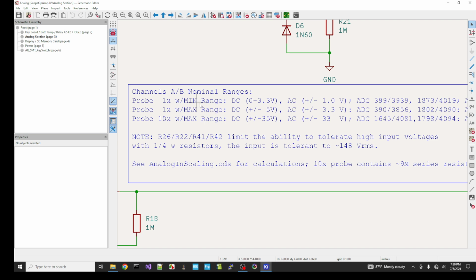On the minimum range, which is the most sensitive, on DC we get 0 to 3.3 volts DC. Then the next range would be plus or minus 5 volts. And then finally, with the 10x probe in the 10x position, we get plus or minus 35 volts. And then AC coupled, as opposed to DC, we get plus or minus 1 volt, plus or minus 3.3 volts, or plus or minus 33 volts.